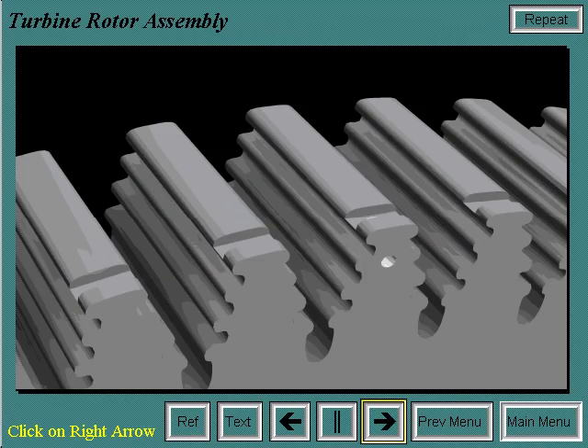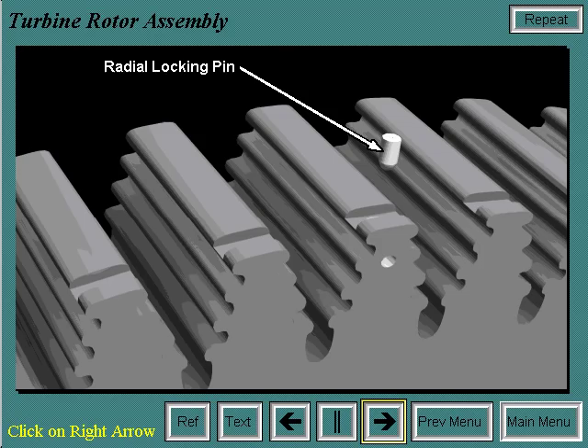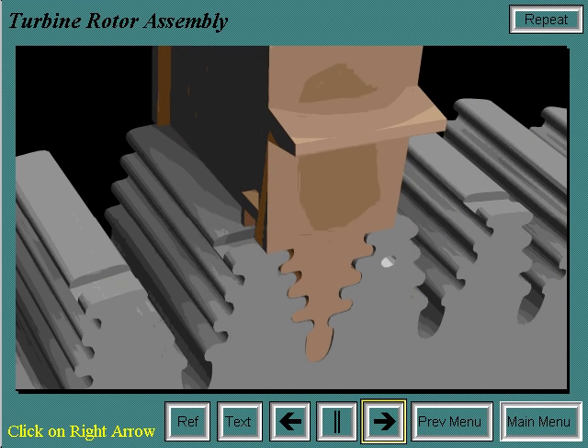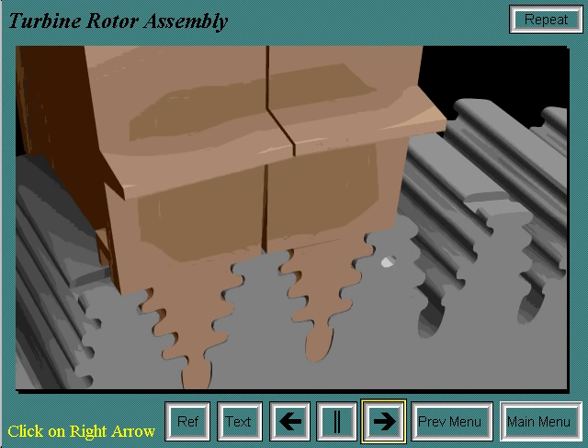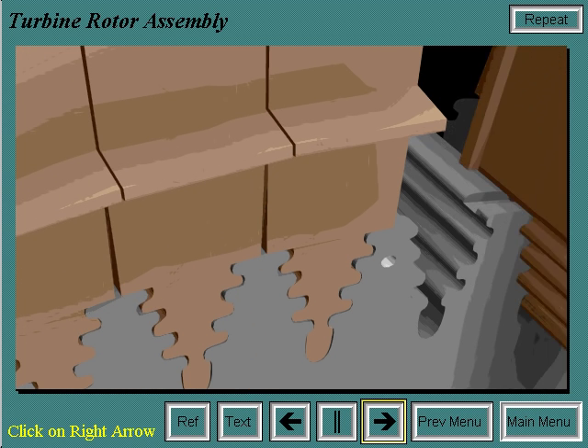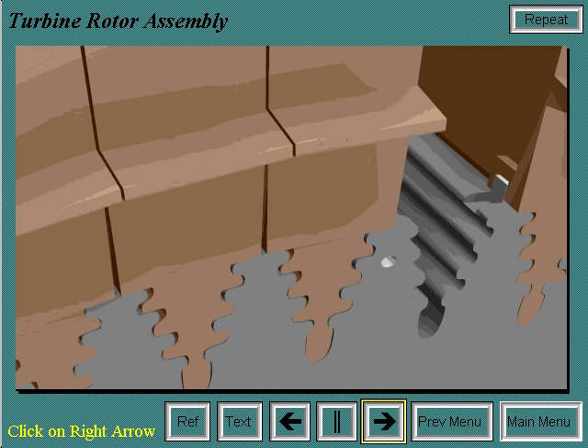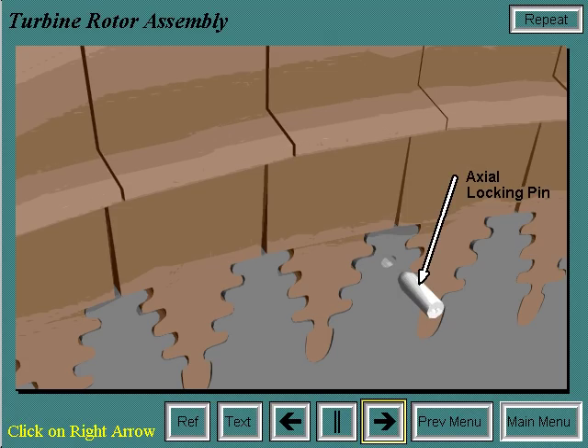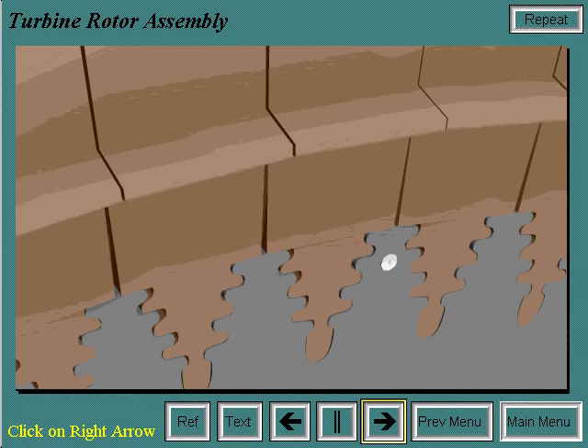The first step of installing the first stage buckets to the turbine wheel is to insert the radial locking pin into the locking bucket dovetail. The first bucket is installed in the counterclockwise adjoining dovetail slot and held in place with a D key. The remainder of the buckets are installed working around the wheel counterclockwise. The last bucket is installed into its dovetail and the axial locking pin is driven into the wheel, pushing the radial locking pin up to hold the last bucket in place.